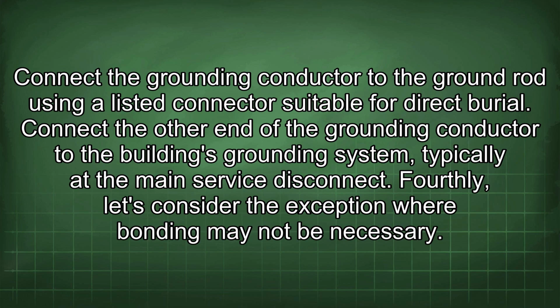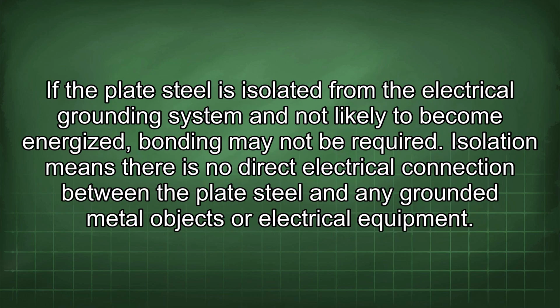Fourthly, let's consider the exception where bonding may not be necessary. If the plate steel is isolated from the electrical grounding system and not likely to become energized, bonding may not be required.